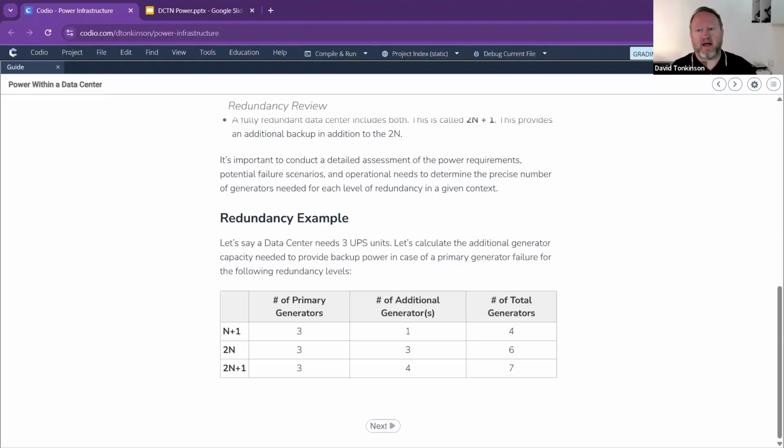In NATS, the UK National Air Traffic Services that I've worked for, their data centers have A and B, essentially their 2N, a duplicated power supply, and they insist they are different manufacturers of diesel generators.